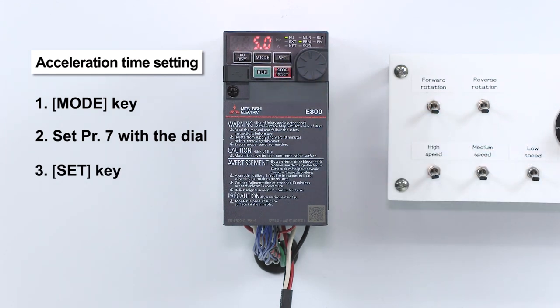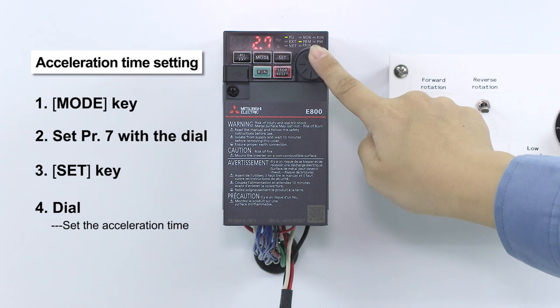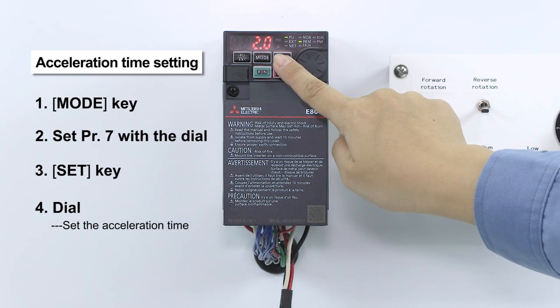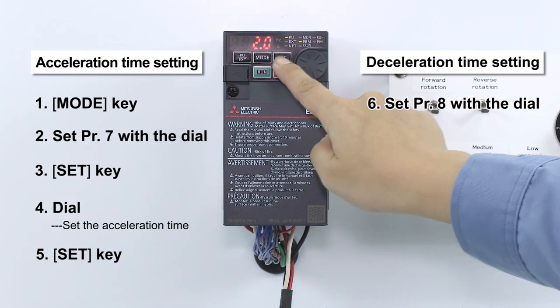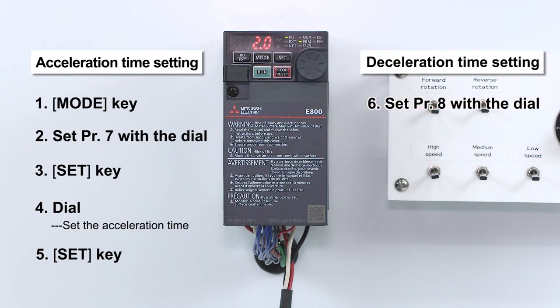Parameter 7 controls the acceleration time from when the motor starts until it reaches the selected frequency. Parameter 8 controls the deceleration time from the selected frequency until the motor stops.